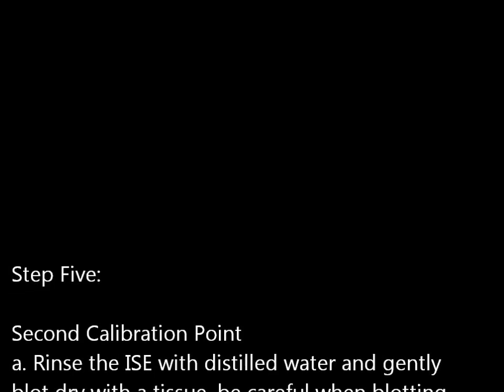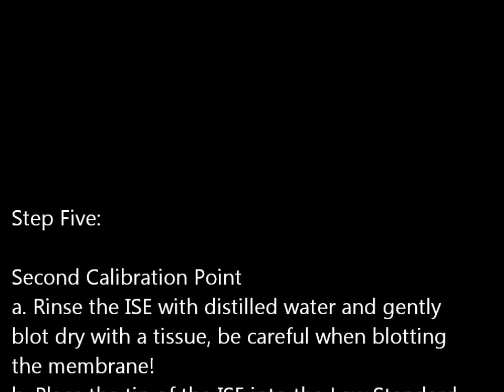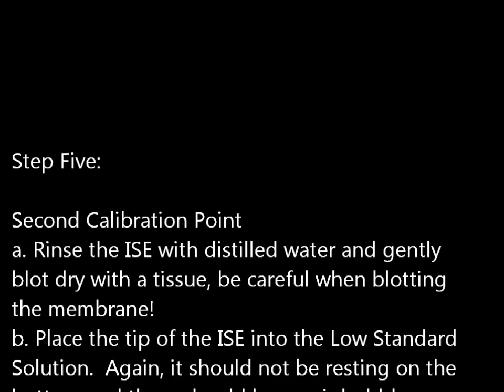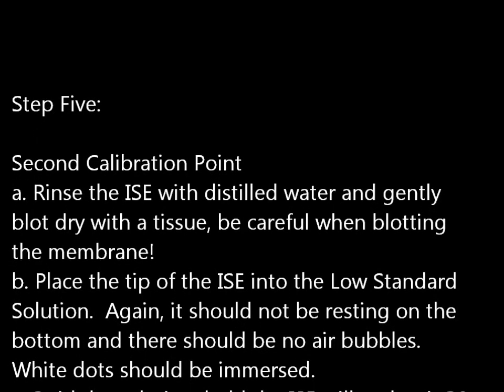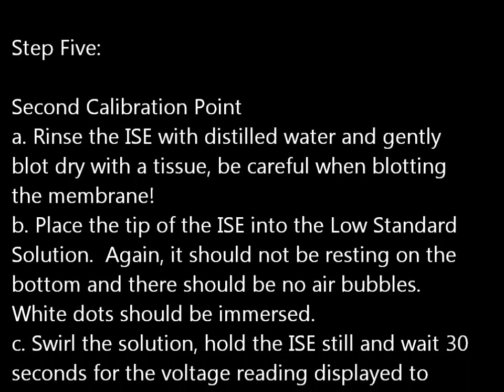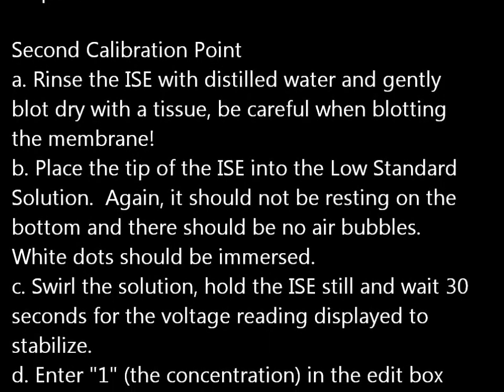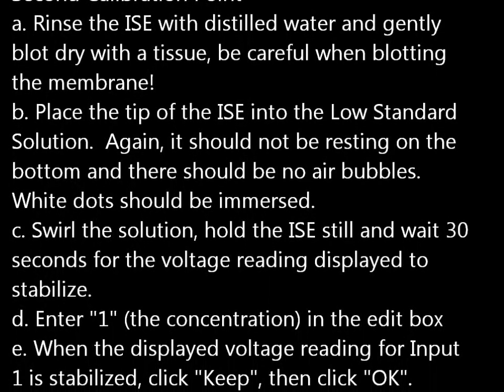Step 5. Second calibration point. Rinse the ISE with distilled water and gently blot dry with a tissue. Be careful when blotting the membrane. Place the tip of the ISE into the low standard solution. Again, it should not be resting on the bottom and there should be no air bubbles. White dots should be immersed.